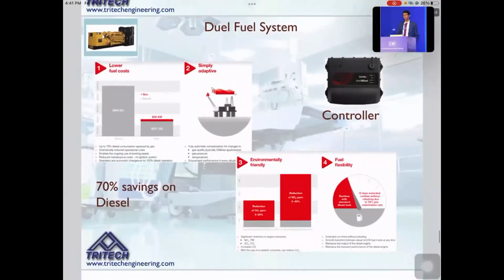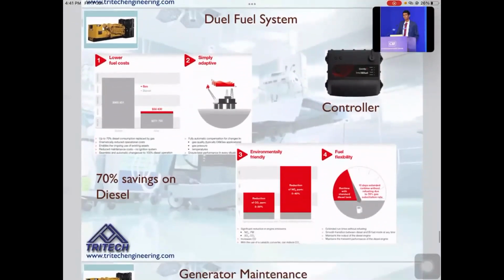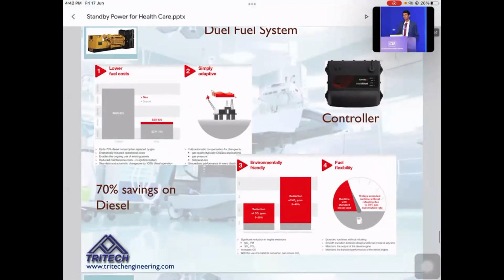Another aspect is the dual fuel system. As you know, diesel is costing above 100 rupees, and CNG costs somewhere around 65 to 75 rupees a liter. These days, there are products available which you can use to convert your existing diesel generators into a dual fuel system by adding a few injectors and controllers. And the controller manufacturers themselves provide the warranty for the system.